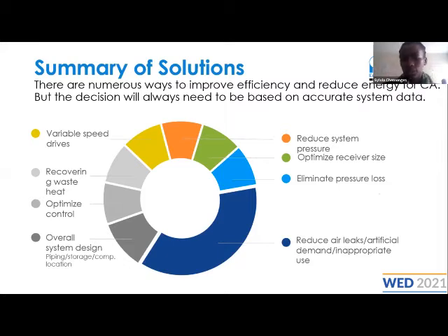And then for your supply side, optimizing your storage would also be very important. Optimizing your storage helps you minimize the number of times the compressor is going to run to meet the demand. So what the receiver does, it buffers supply from the compressor. The compressor runs, supplies enough compressed air to the receiver, then it stops running. So air is going to be consumed from the receiver, and energy consumption from the compressor is going to be low.